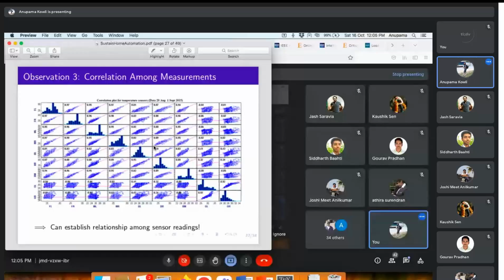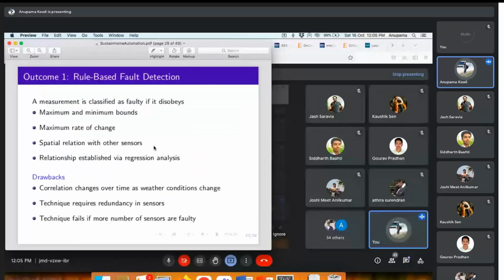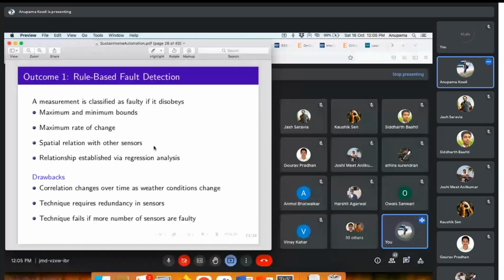So what we did, for example, was look at a sensor and how we were measuring readings, every 5 minutes. Now, if I'm sensing a temperature of 26 degrees in this minute, and in the 6th minute it suddenly jumps to 32, is that even feasible for that sensor in that given location? This is something you can try to learn over time, through a rule-based mechanism. And so this is where the rate-of-change rule can be applied.